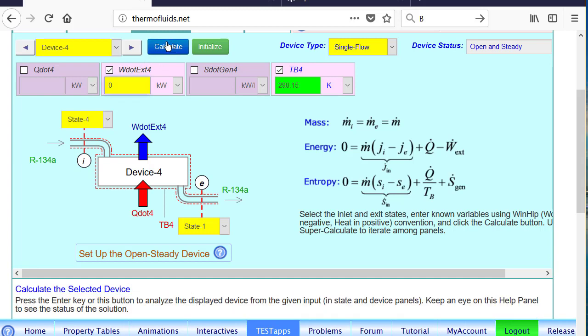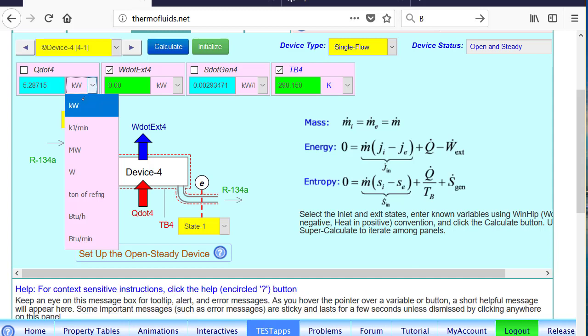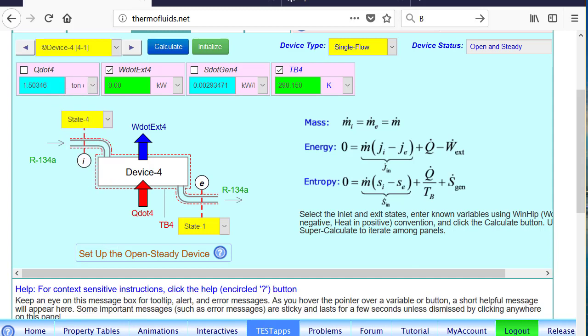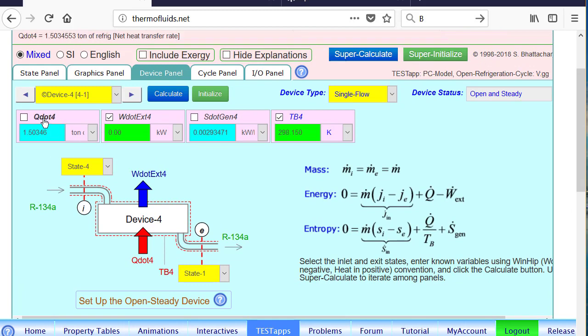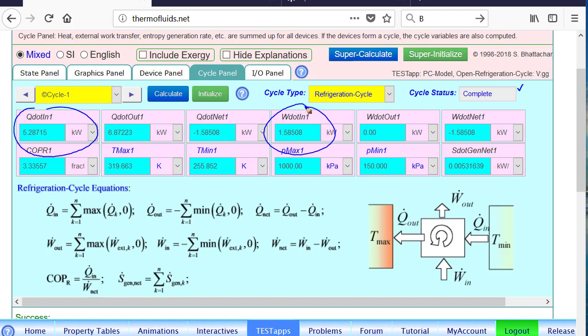So 5.28 kilowatt is our cooling load. If we convert it to ton of refrigeration, that is our answer. We could also go to the cycle panel — because the cycle is complete, we can pick up our answers there too. Q dot in is our desired answer in kilowatt, but you can switch it to tonnage. W dot in is the compressor work, and you can also find the maximum and minimum temperatures in the cycle.